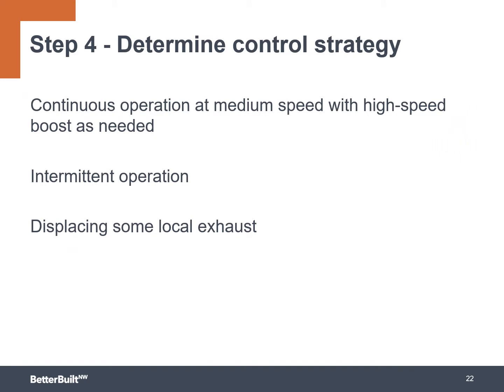Now, you can make an argument that step 4, determining the control strategy, could actually be step 3. It's a little bit interchangeable here, because we're really talking about making the decision of whether or not we want to do continuous operation, which allows us to use medium speed and then have a high speed boost as needed. Or do we want to do this as intermittent, and do we have the ability to displace some of our local exhaust?